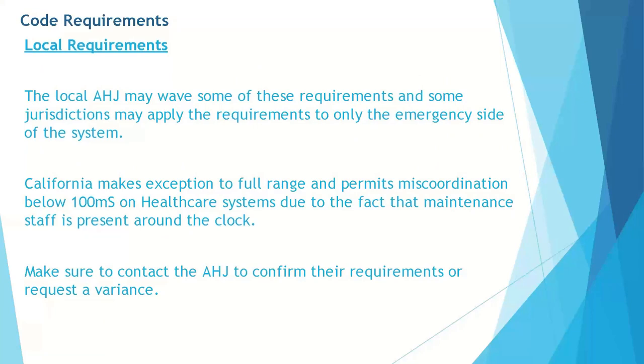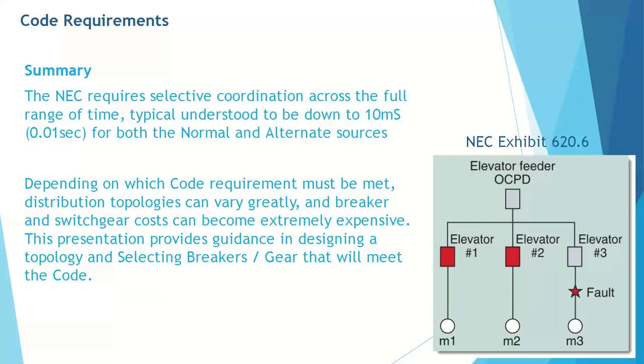Sprinkled in related sections are ground fault protection selectivity requirements, but we will focus this discussion on phase protection. For COPS systems in 708.54, again states all supply side devices. For elevator systems, we have section 620.62 that phrases it slightly different with any other supply side devices. Any other is understood to be the pathway all the way back to the source. I want to point out that as with series rating of elevator systems, there is no exception in this section for devices in series as we saw previously with emergency or legally required.